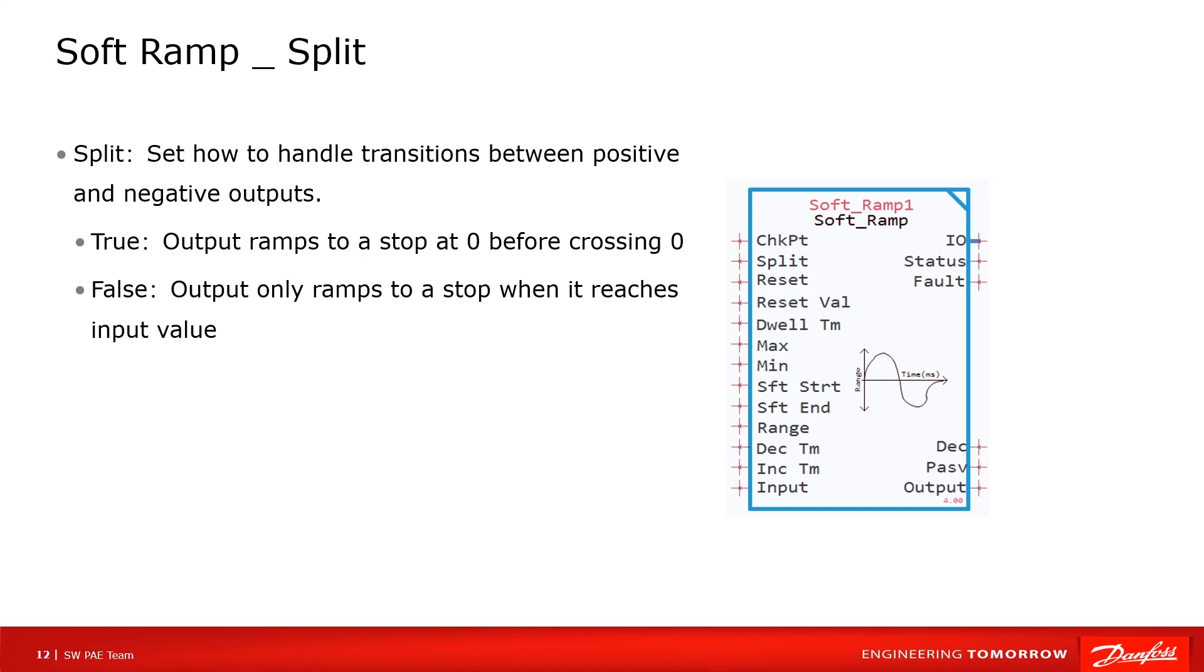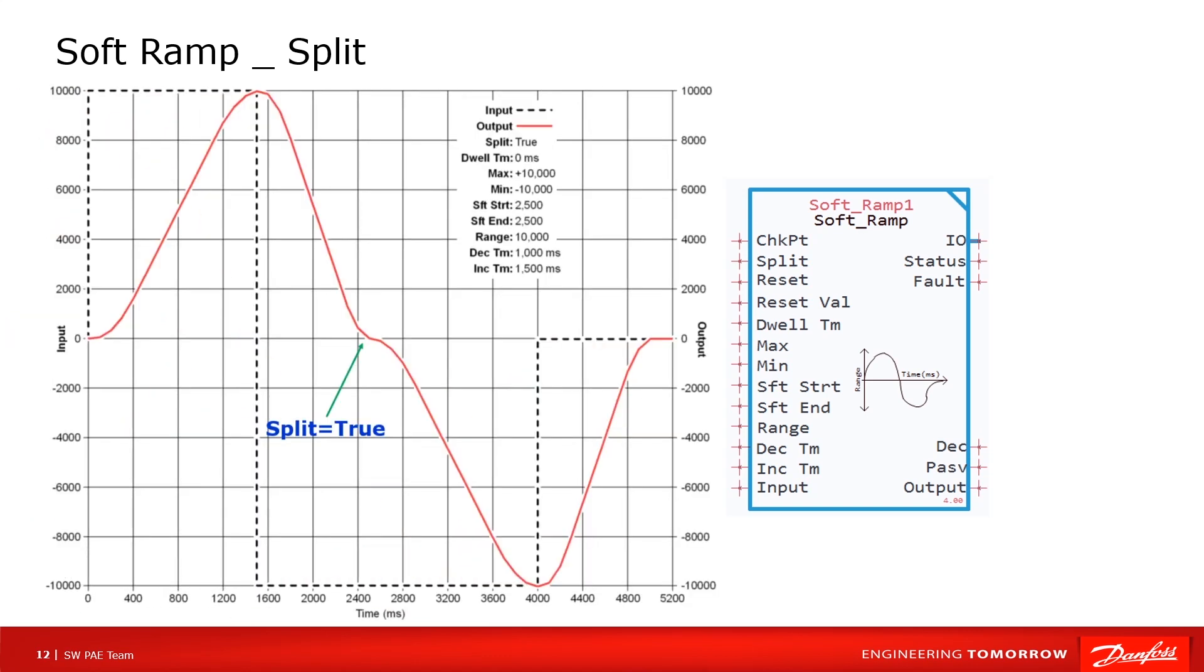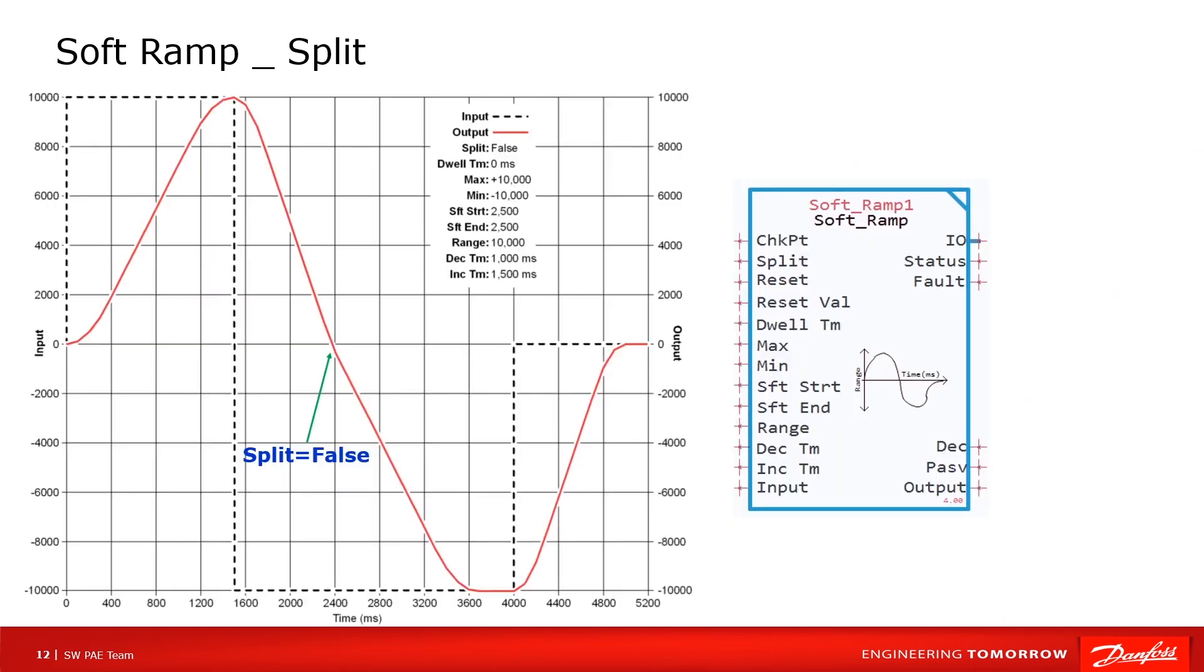Split. This parameter determines how to handle the acceleration when direction changes. Let's look at the trace. If split is true, output soft end to zero, then soft start in another direction. If the split is false, there will not be soft end and soft start.